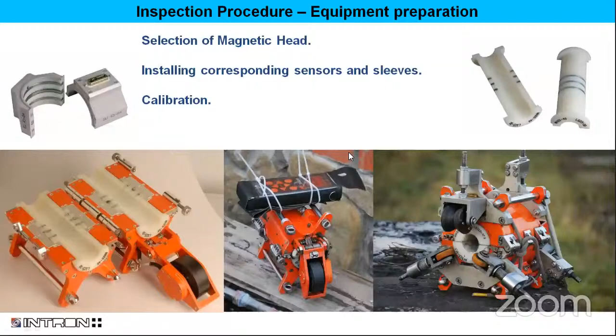So let me run you through a typical inspection. First of all, you need to prepare the equipment. By this, obviously, selecting the magnetic head suitable for the rope diameter, installing the necessary sensors and plastic sleeves, and calibrating the unit. Now, for calibration, you need 2 reference points.